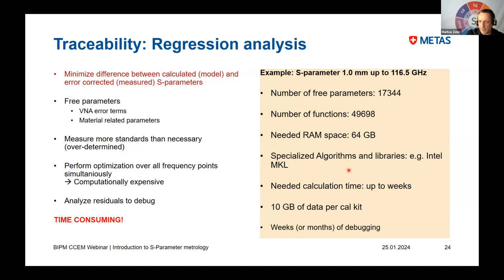For other connector families which don't go that high in frequency, it maybe can be done in 1 or 2 days. At the end, you have about 10 gigabytes of data per calibration kit. And the debugging is usually the most time consuming. This can go weeks, or we had cases when it went for months. Okay, so that's my final one.